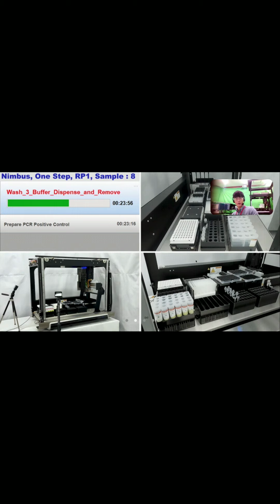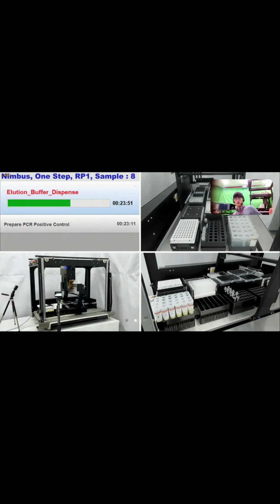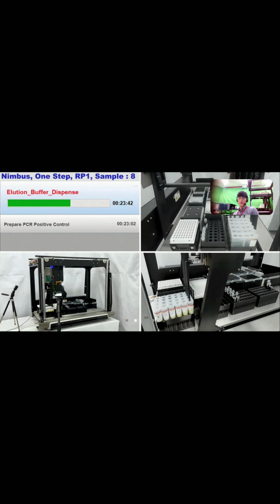Okay, at this time, we need to measure another one. I have 8 samples. In this video, there are 8 samples. When the final position of the sample is dispensed, aspirated, and the tip is ejected, at this moment just click the pause button and take it out. Both the tip well plate and the magnet, measure again. It should be less than 10 microliter.